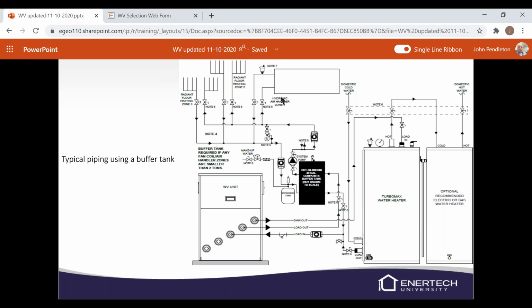If we have an air handler that's smaller than 2 tons, then we want to go to the buffer tank instead of the hydraulic separator. And again, we're going to have an external pump for your zones, some flush blocks on your external piping, and an air vent on your high point of the system. And then again, it decouples the pumping needs for the unit and the pumping for your zones.